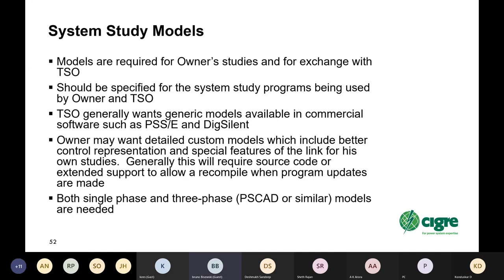And system study models, this is an important area to specify, because models are always required for the owner studies subsequent to the delivery of the HVDC system and for exchange with the transmission system operator. The models should be specified for the system study programs being used by the owner and the transmission system operator. The TSO generally wants generic models that are available in commercial software such as PSS/E and DigSilent, and doesn't want to worry about specific user models if possible.